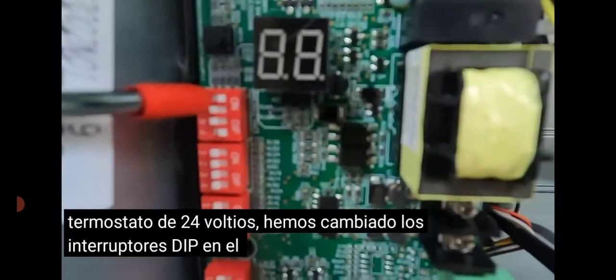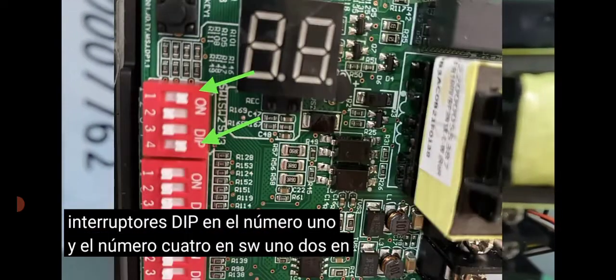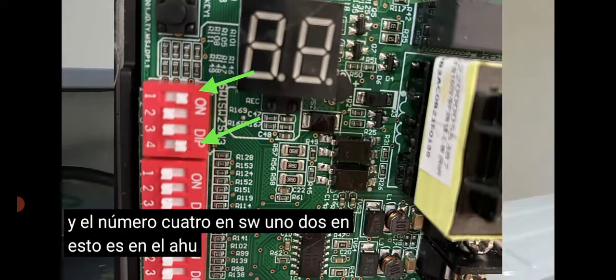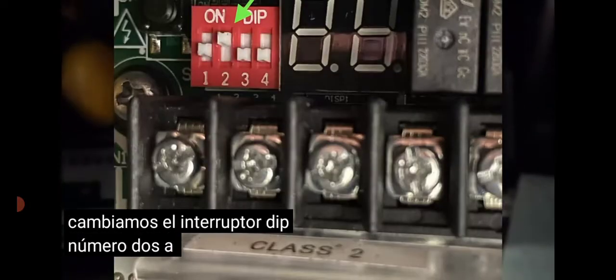Now for this 24-volt thermostat, we have switched the dip switches at number 1 and number 4 on SW1 to on. This is at the AHU. Moving over to the CPR, we switched over the dip switch number 2 to on.